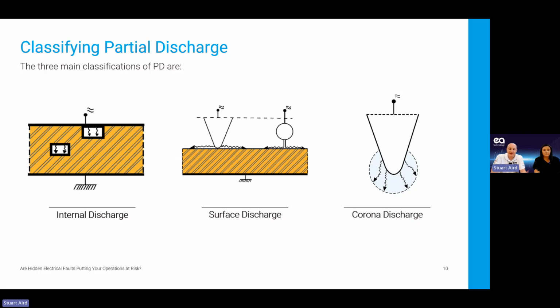If you think about how we're going to detect it, we think about the emissions from the last slide. Inside that air pocket there will be a sound, you'll hear that arc, you'll have the light, you'd have the different emissions. But ultimately, we can't pick that up with a sensor while it's in normal operating condition, because that's all kept within that void. So the only realistic way to detect an internal partial discharge outside, non-intrusively, while it's in normal operating condition, is through the electromagnetic waves that are created by that partial discharge event.